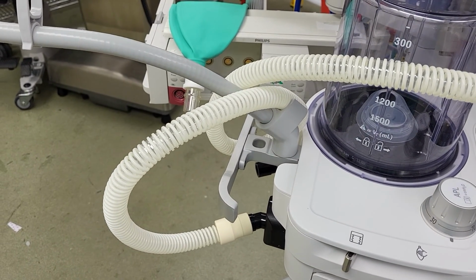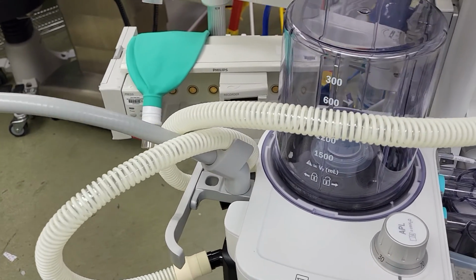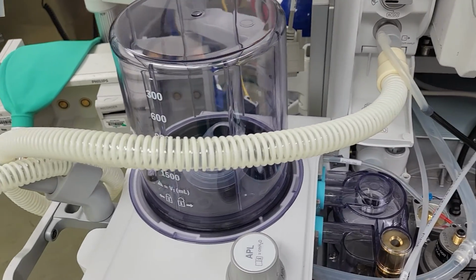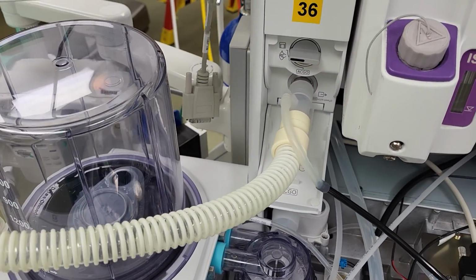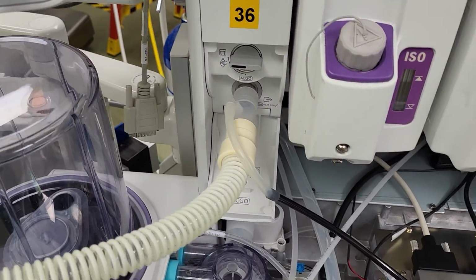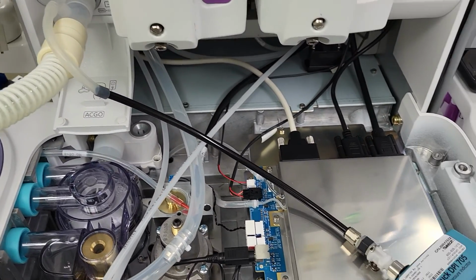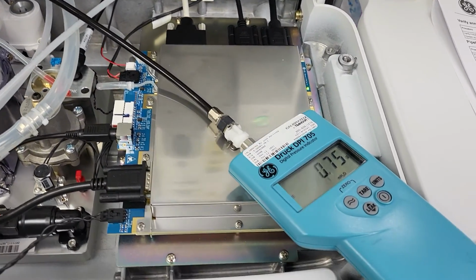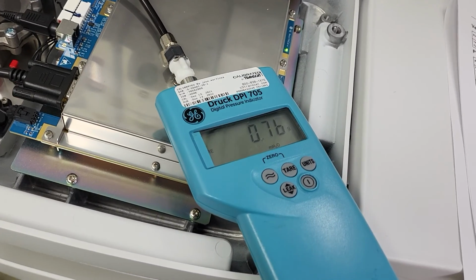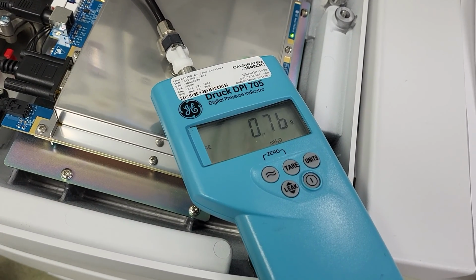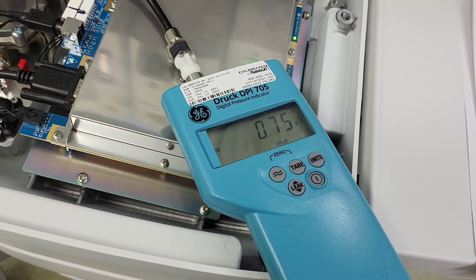See right there? That tubing that goes from the inspiration port to the patient all the way over to the ACGO with a T in place. And that T's in there so we can T in the pressure gauge. So here's our pressure gauge, and there it is, 75, 76, teetering. See that? That's the key to this calibration.